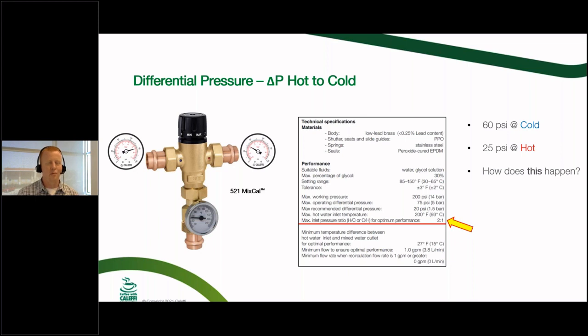But why is it necessarily a problem? The fact is that the mixing valve, in order to work and perform properly and work well, those pressures need to be as equal as possible, because the more of a difference there is, the less effective the mixing valve is going to be, and the less resolution it's going to have as far as making its adjustments and everything like that. And you're going to start getting some erratic temperature changes in there as well. But the biggest one typically we run into is the fact that the mixing valve just doesn't give me hot water anymore, okay? Maybe it's instead of 120 degrees, it's giving you 105 or 95, but you know full well that your domestic hot water source is sitting at 120 or 140.